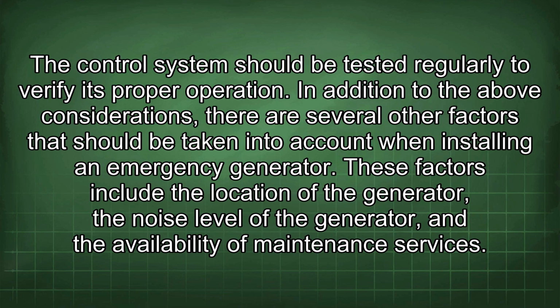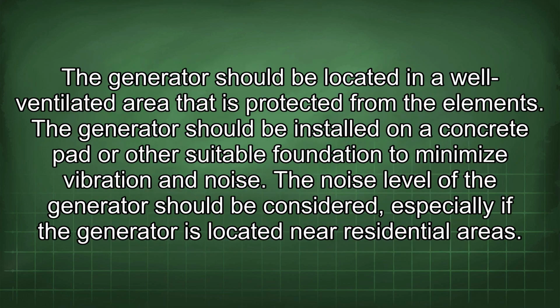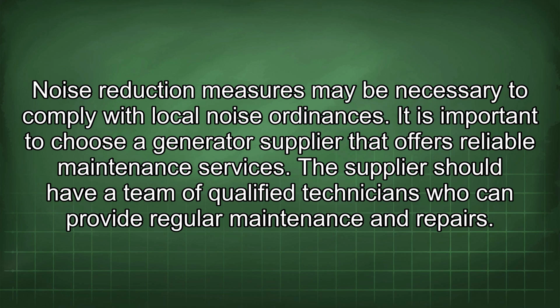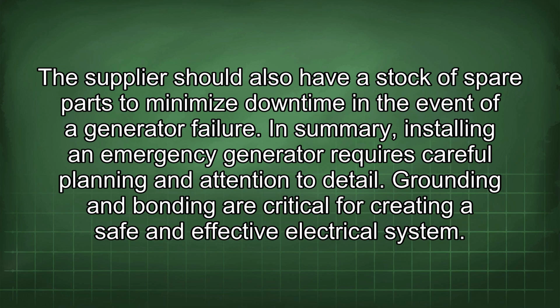maintenance services. The generator should be located in a well-ventilated area that is protected from the elements. The generator should be installed on a concrete pad or other suitable foundation to minimize vibration and noise. The noise level of the generator should be considered, especially if the generator is located near residential areas. Noise reduction measures may be necessary to comply with local noise ordinances. It is important to choose a generator supplier that offers reliable maintenance services. The supplier should have a team of qualified technicians who can provide regular maintenance and repairs. The supplier should also have a stock of spare parts to minimize downtime in the event of a generator failure.